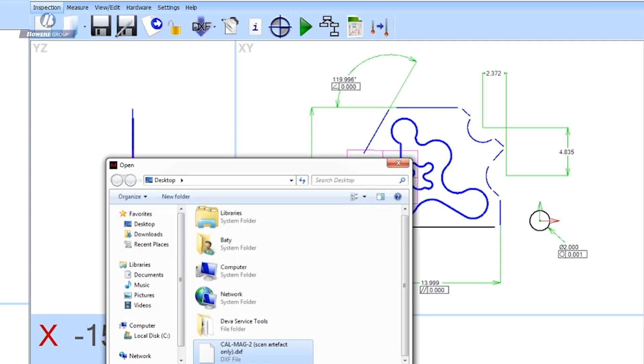So, having used the curve profile scanning tool to create this point cloud, what are we going to do with that data? Well, the most convenient way of using that data, I think, is to import a DXF file so that we can compare the data to the CAD profile and see how close it is to the nominal profile. Profile projector users would relate to this in terms of an overlay, the transparency that you would actually place onto the optical comparator to try and find a fit between the projected image and your drawn image. The DXF is basically an electronic version of that. So let's bring in a DXF of that shape.